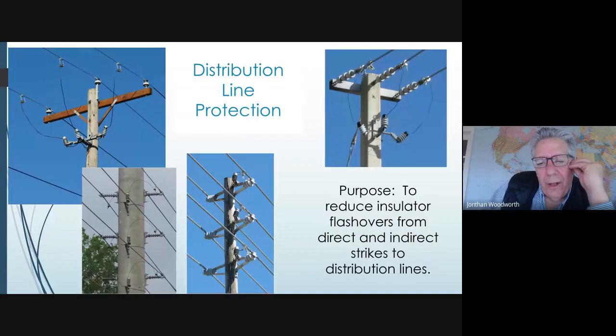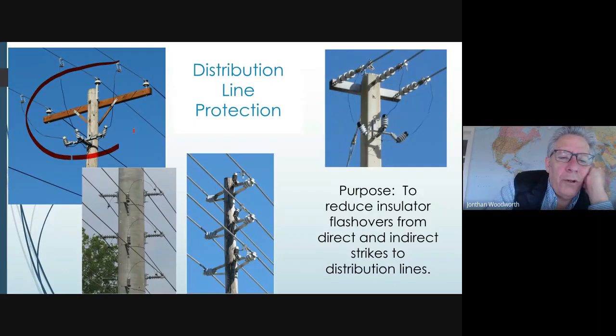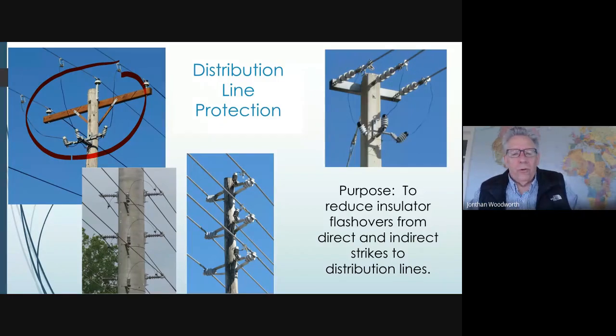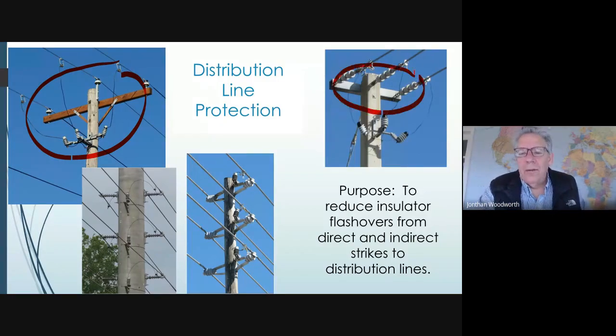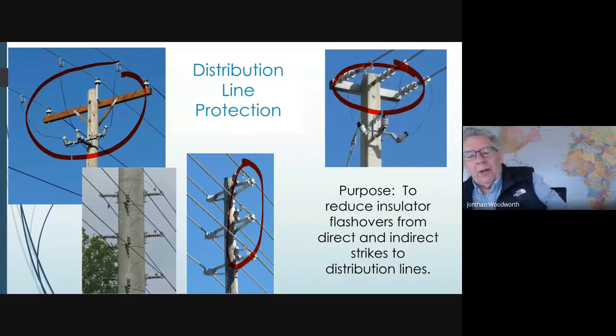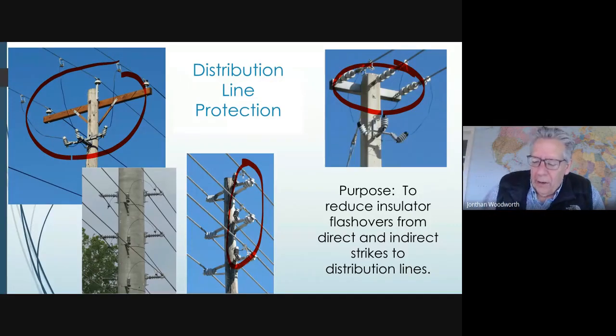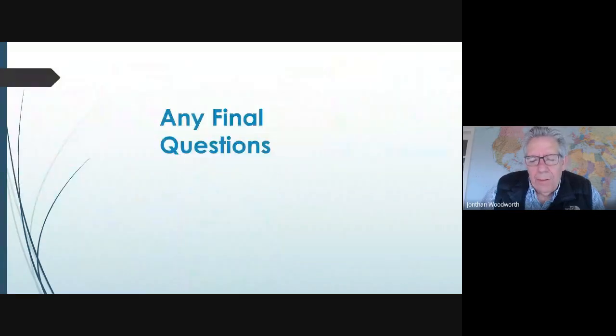On protection, on distribution lines, oftentimes we see arresters applied just to keep these insulators from flashing over, at the end of lines, sometimes on one side of the circuit. So line protection is more popular in the higher lightning areas than in lower lightning areas. And I think that's it.